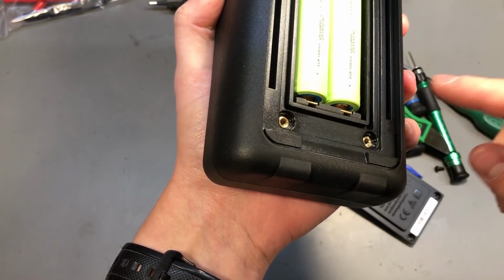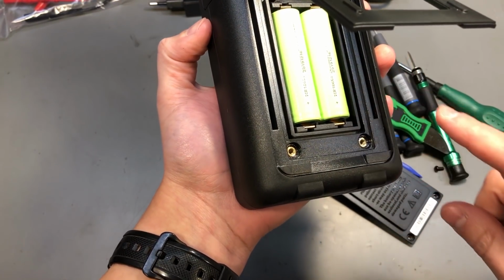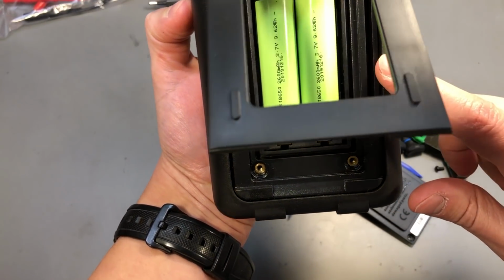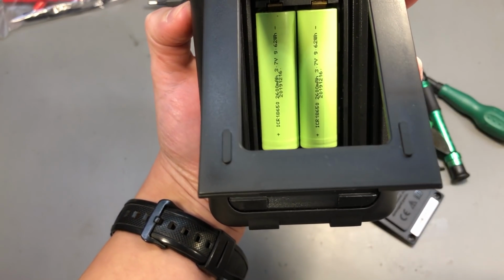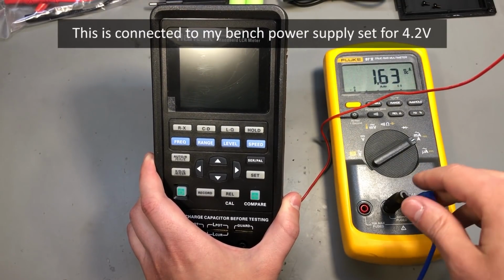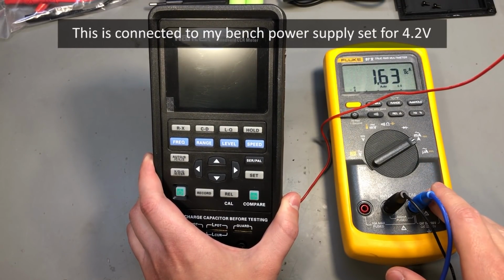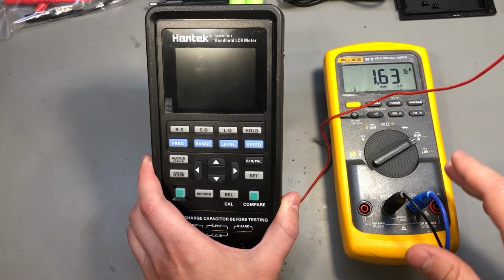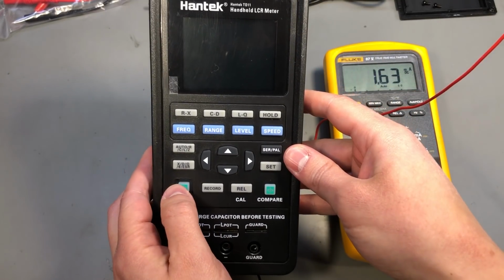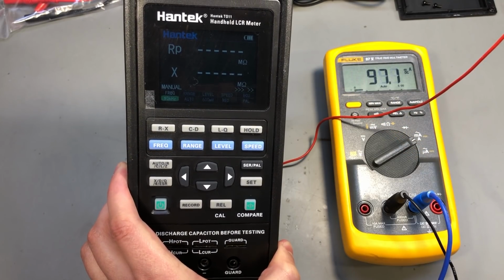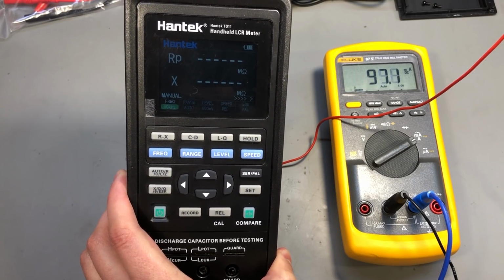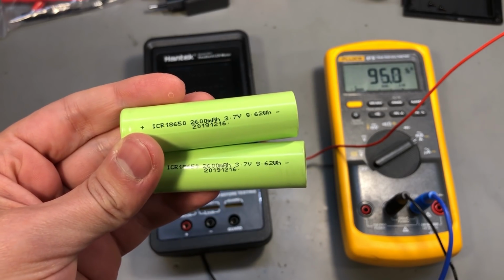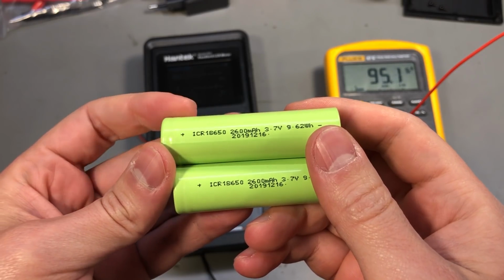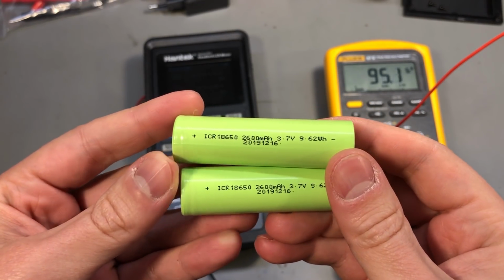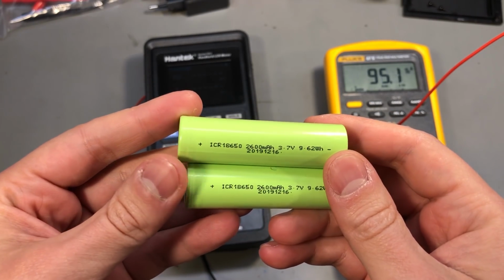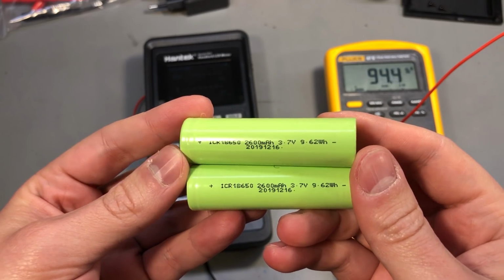So let's measure the current consumption of the instrument to figure out the battery life we're going to get with two of these cells. And we're seeing about 1.63 milliamps of current being pulled in standby. Let's turn it on. And we have about 97 milliamps while the meter is active. The batteries used in here are rated for 2600 milliamp hours each, and we have two in parallel, so that's 5200 milliamp hours total capacity.